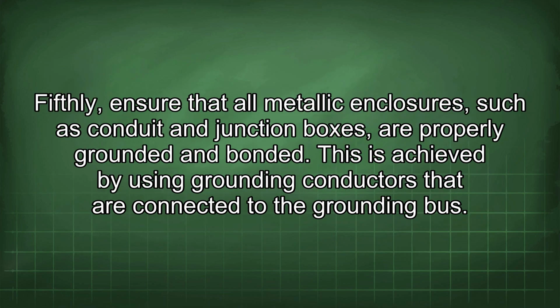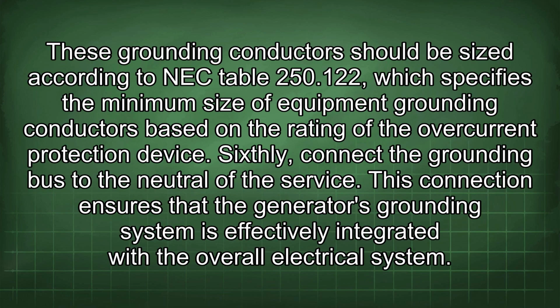Fifthly, ensure that all metallic enclosures, such as conduit and junction boxes, are properly grounded and bonded. This is achieved by using grounding conductors that are connected to the grounding bus. These grounding conductors should be sized according to NEC Table 250.122, which specifies the minimum size of equipment grounding conductors based on the rating of the overcurrent protection device.